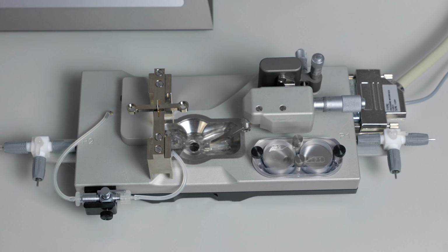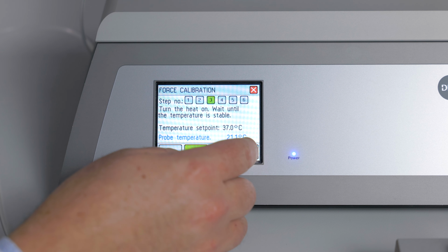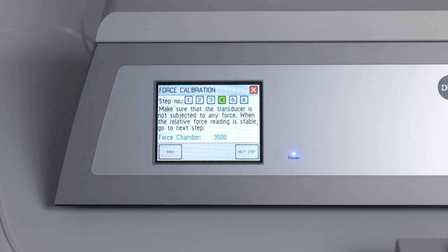The transducers are temperature compensated, meaning that they are designed to work at 37 degrees. You can perform the force calibration at room temperature. However, you must make sure that you are not actively warming the chamber while you are doing the calibration. The warming takes about 20 minutes, so make sure that you have either pre-warmed the chamber or leave the heat off. Press next step. Step 4 wants you to make sure that the transducer is not subjected to any force. This 4-digit number should be stable and not drifting in any direction. If it's going back and forth between two numbers, that's fine.